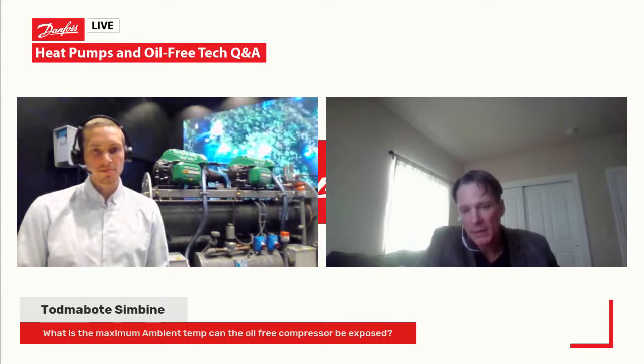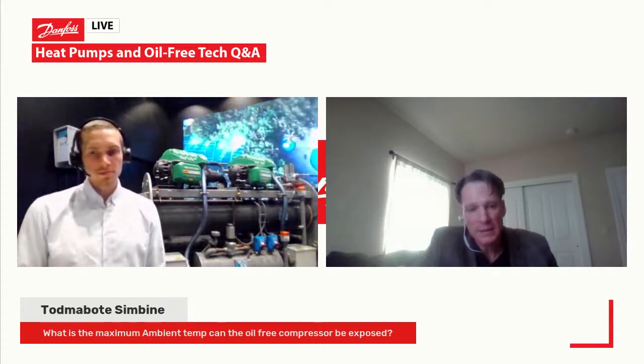In general, if it's a really high ambient application, either in an unconditioned equipment room or outside where it gets extremely hot, most of our OEMs will build the compressor into some type of enclosure. It doesn't need to be high-end, but it's a good idea to protect it. It's not absolutely critical, but I believe that recommendation is part of our application manual. I'll come back to you with a very specific number from the latest version.